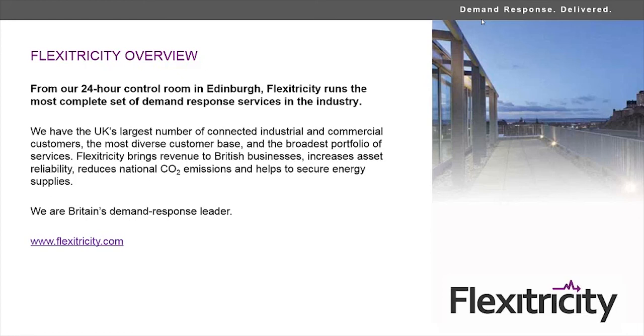Then a question specifically about DRUPS units that are used for frequency control. Are these classed as tranche A, tranche B, or an excluded generator? For frequency control, if you're not offering the service to National Grid and you're running less than 50 hours a year, you're excluded, probably. And if you have a contract with National Grid through an aggregator or through yourselves, then that's classed as a balancing service. So if it's a contract that was signed before Halloween last year, then it's tranche A, and if it's a new contract, then you're a tranche B generator. So you'll need to comply by January 2019.